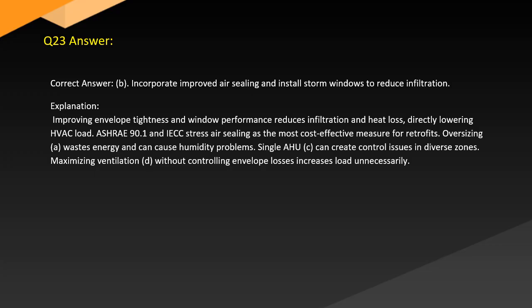Answer. Correct answer: B. Incorporate improved air sealing and install storm windows to reduce infiltration. Explanation. Improving envelope tightness and window performance reduces infiltration and heat loss, directly lowering HVAC load. ASHRAE 90.1 and IECC stress air sealing is the most cost-effective measure for retrofits. Oversizing, A, wastes energy and can cause humidity problems. A single AHU, C, can create control issues in diverse zones. Maximizing ventilation, D, without controlling envelope losses increases load unnecessarily.